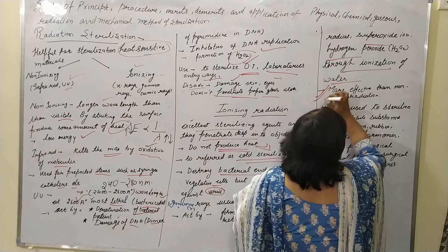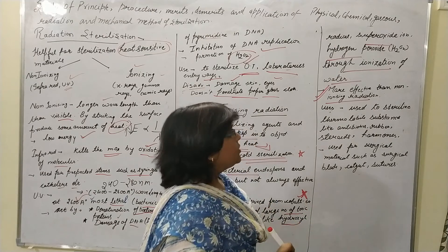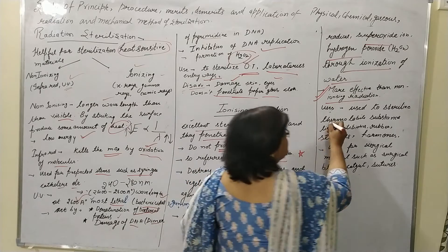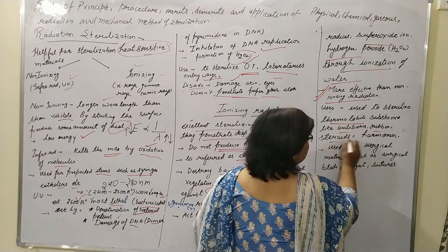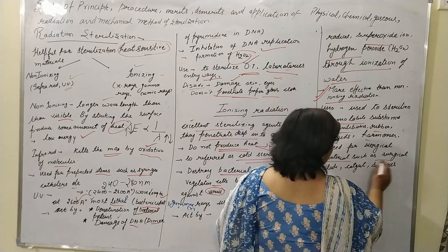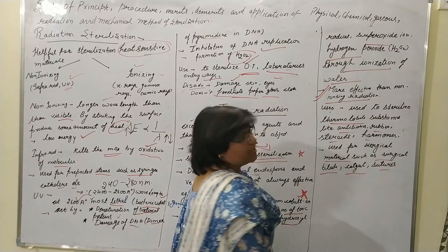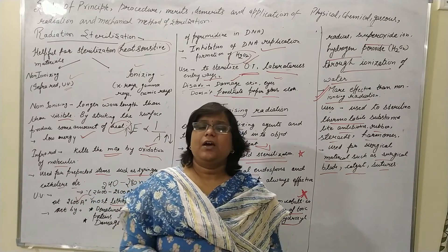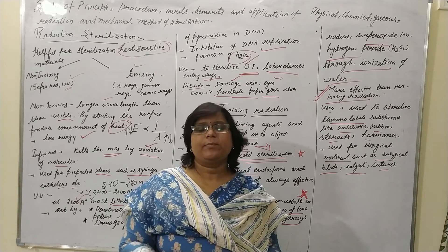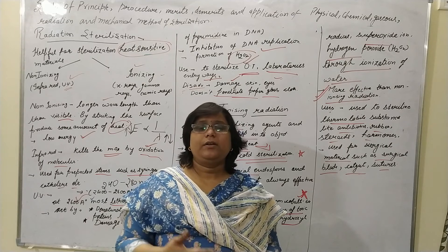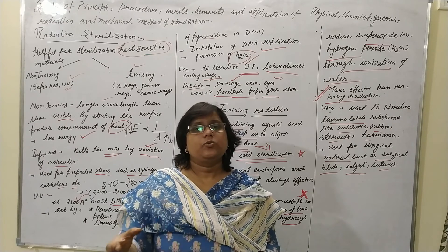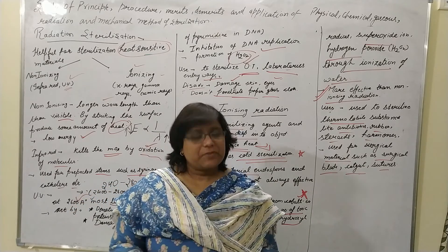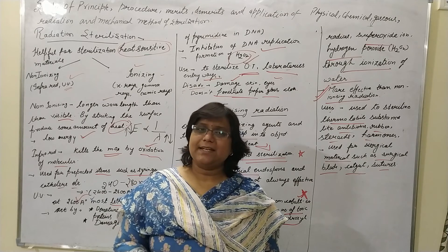Ionizing radiation is more effective than non-ionizing radiation. It is used to sterilize thermolabile substances like antibiotics, rubber, steroids, and hormones, as well as surgical instruments like surgical blades, catgut, and sutures. However, not all materials are suitable for radiation sterilization, and not all radiations are able to destroy endospores.